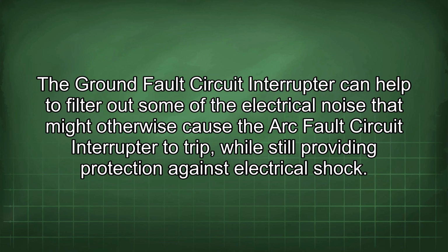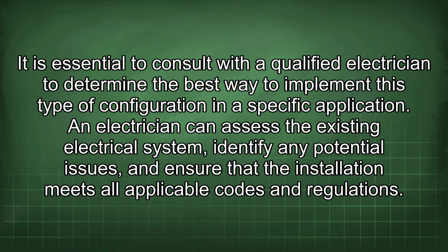The ground fault circuit interrupter can help to filter out some of the electrical noise that might otherwise cause the arc fault circuit interrupter to trip, while still providing protection against electrical shock. It is essential to consult with a qualified electrician to determine the best way to implement this type of configuration in a specific application.